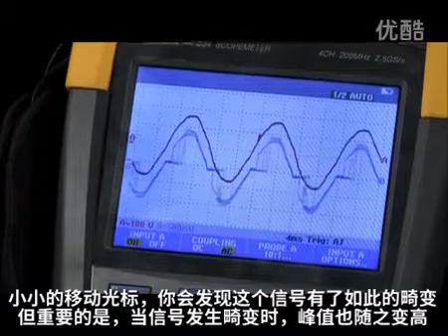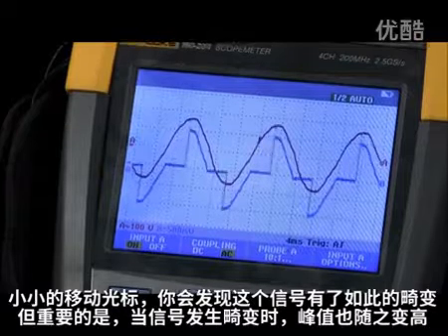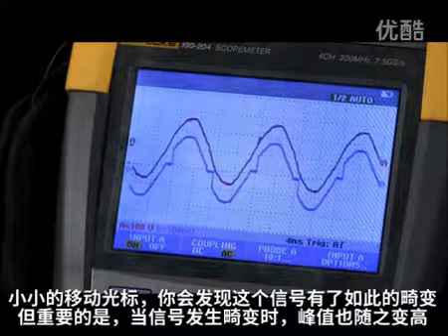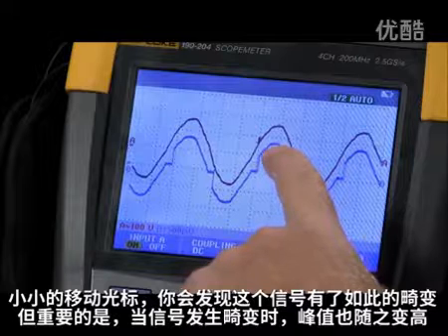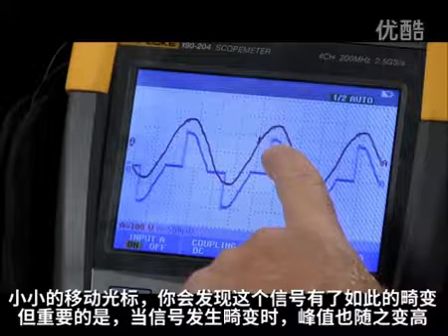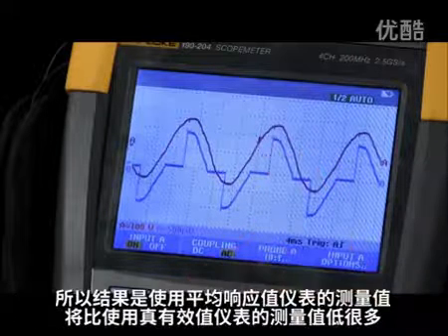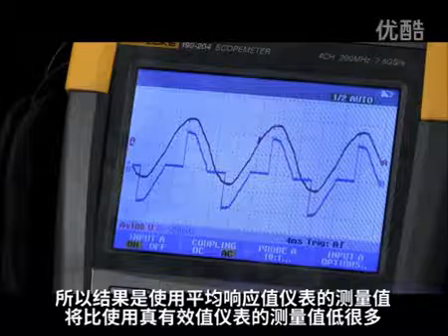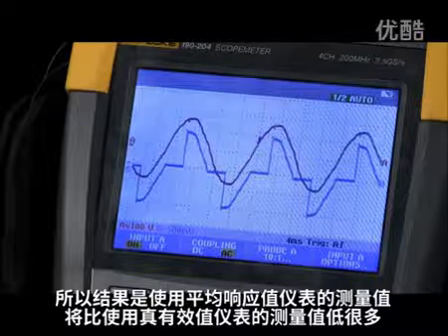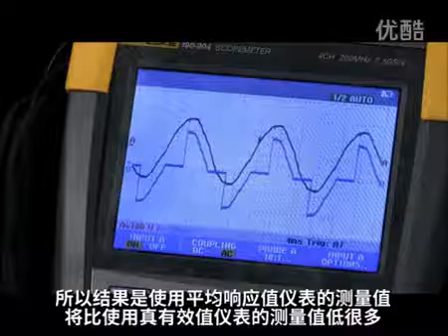Even just taking this dimmer switch, you notice how the signal gets distorted, but an important aspect is as it gets distorted, the peak gets higher. So what happens is you'll actually read a signal too low with an averaging RMS versus a true RMS.